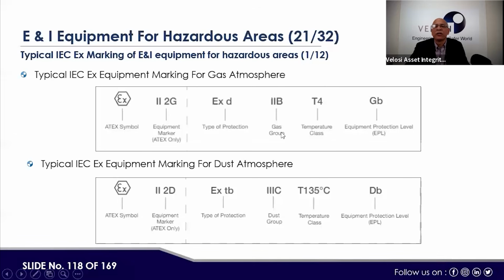So three things: gas group, temperature, or level of protection. IIB, T4, Gb. Similarly, if you take typical equipment marking for a dust atmosphere, it is the same: Ex tb, then IIIC, the dust group, T135 degrees temperature class, and Db. So practically, we are worried about these three things: what the gas group is, what the temperature class is, and the protection level.